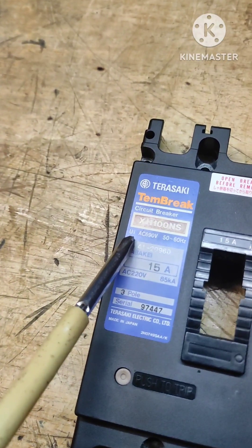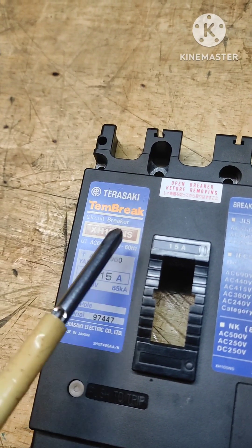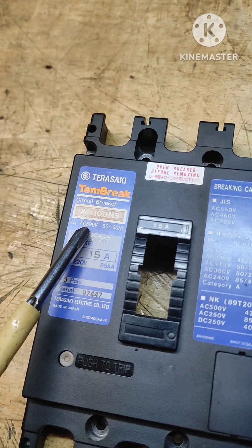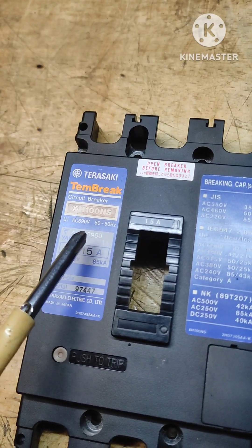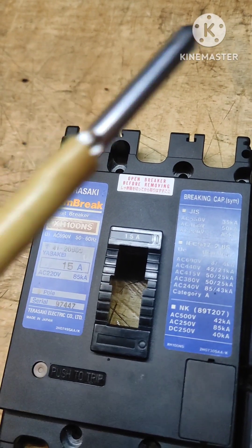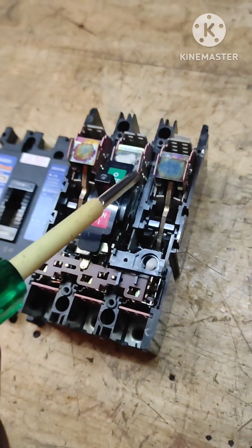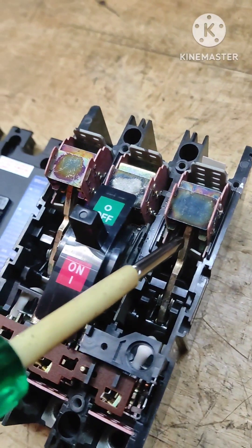Here it is written Ui — rated insulation voltage — that is AC 690 volts. That means when this was manufactured it was tested for 690 volts and withstood, so its insulation can withstand up to 690 volts. This indicates the frequency, some model numbers of the company, and 15 amperes, three poles — because it has three poles: one, two, three.